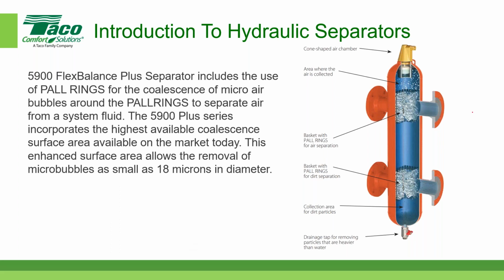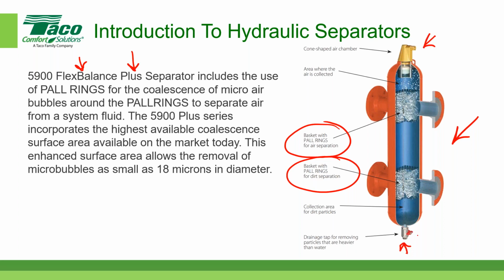So if you notice the little picture on the right is almost identical to what we had before, only this time we have the basket with the Pall rings, and we have two sets of baskets. And that means that this hydraulic separator, which is called the 5900 Flex Balance, and we have the word plus in there, acts not only as a hydraulic separator, but it also acts as an air vent at the top and a blowdown at the bottom. So it's an air and dirt separator. So it's a three-function device. It's a hydraulic separator, it's an air separator, and a dirt separator.